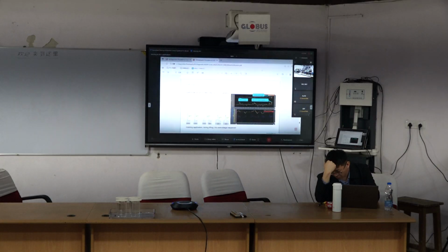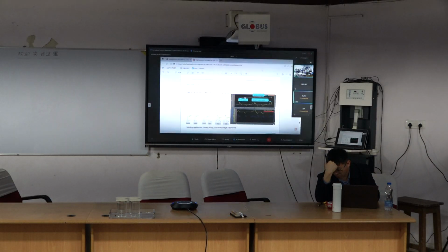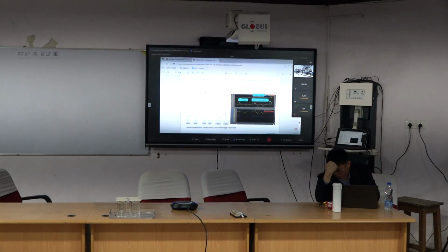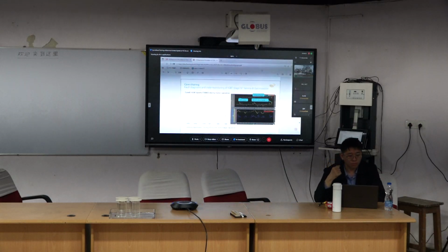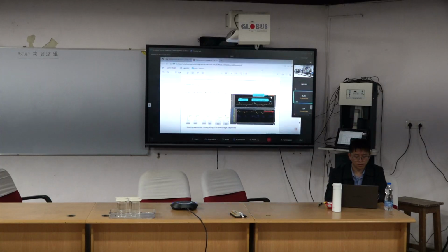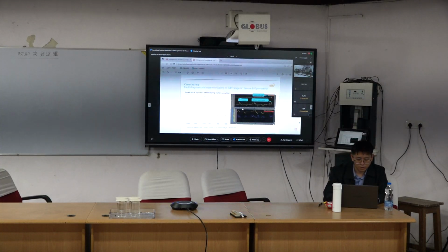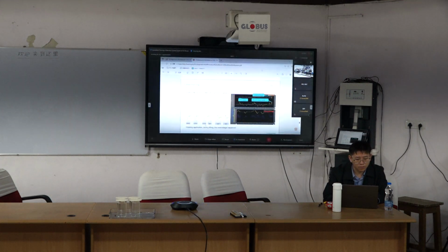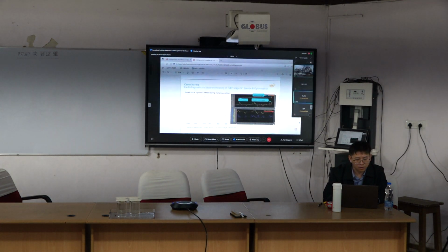But in this field case, overvoltage happens. You can see the ALM enabled, running load, in motor mode with active power greater than 0. But overvoltage happens. This is a lifting application, a hoisting application.